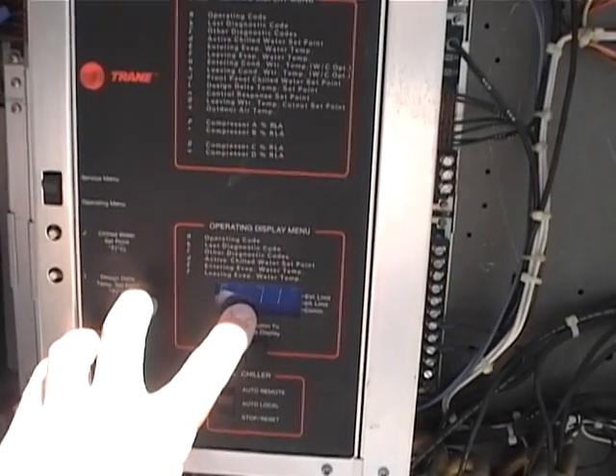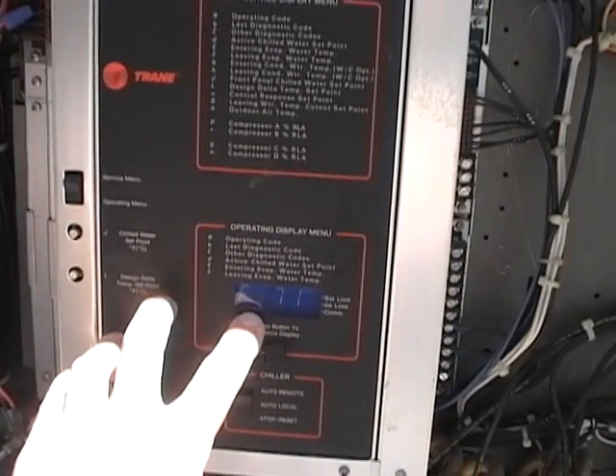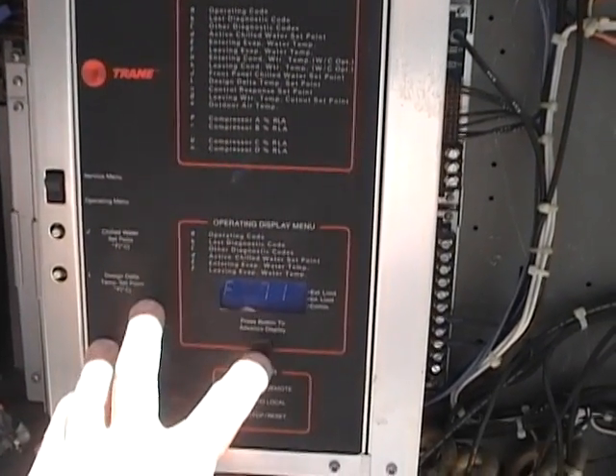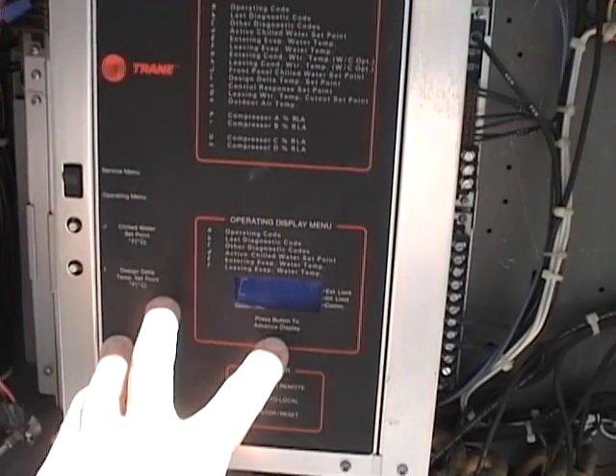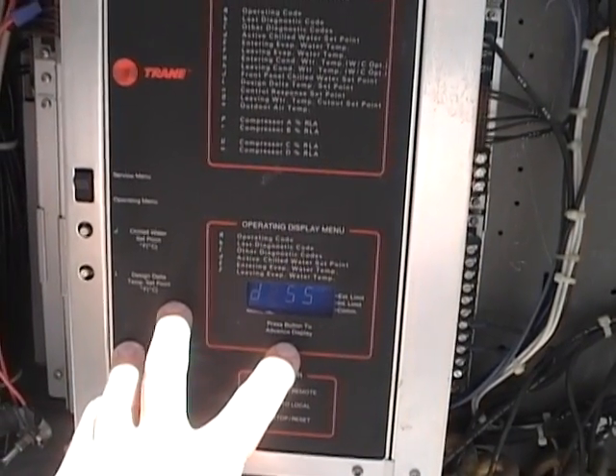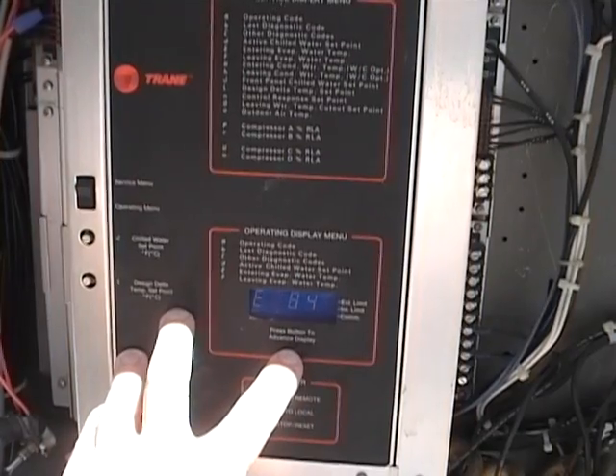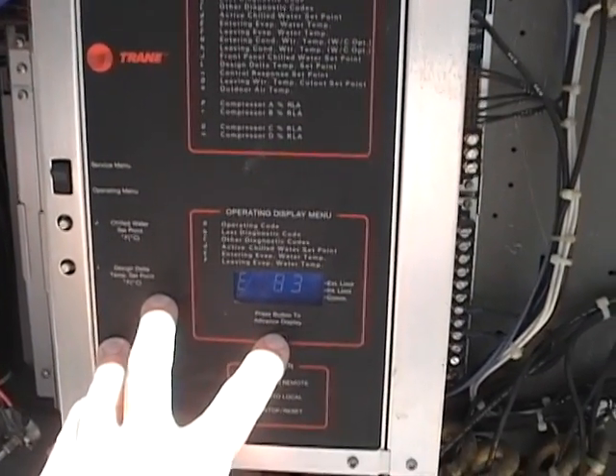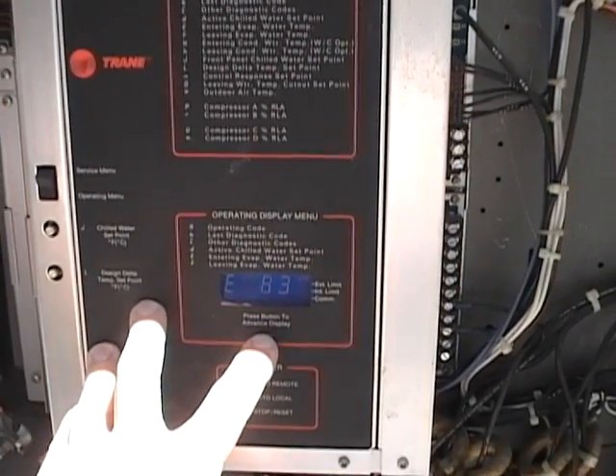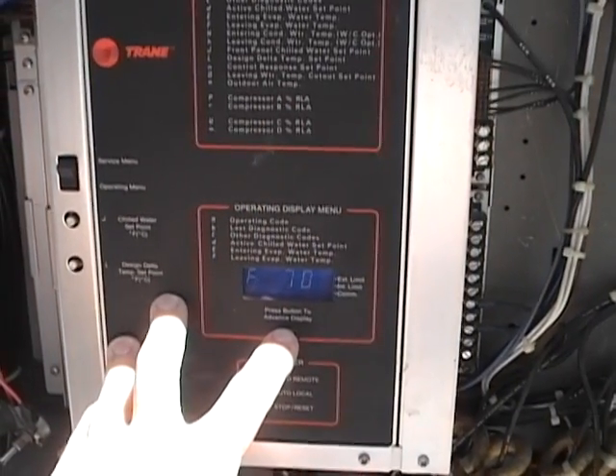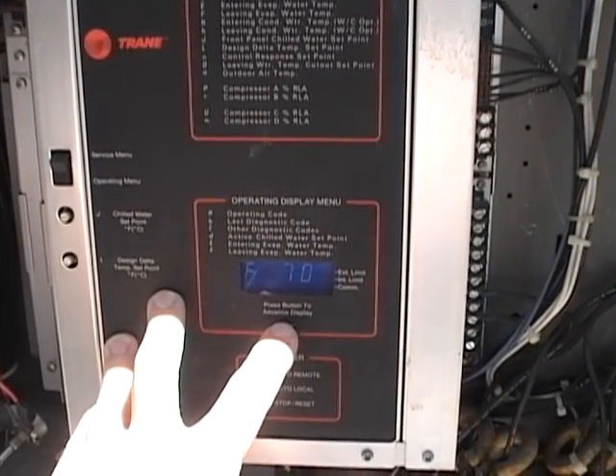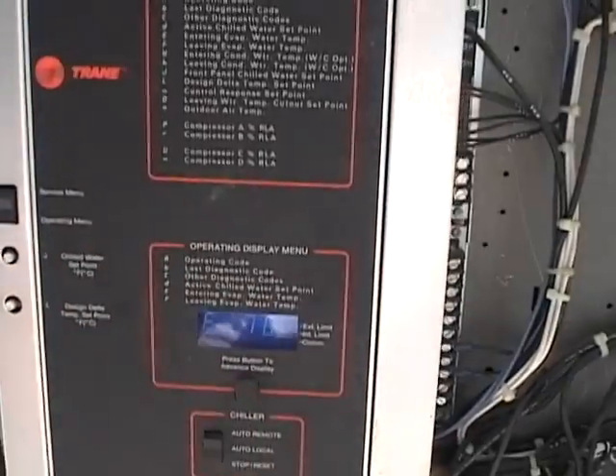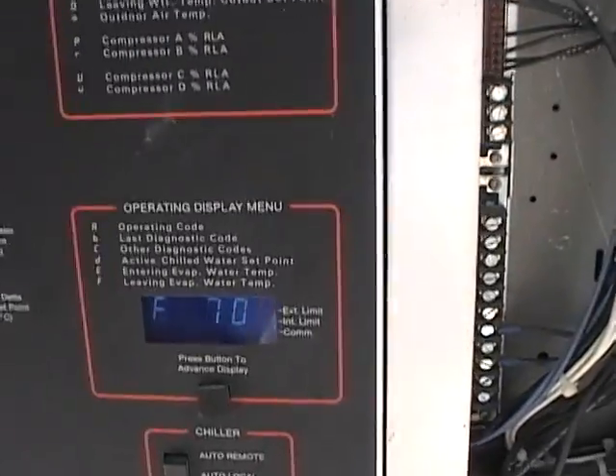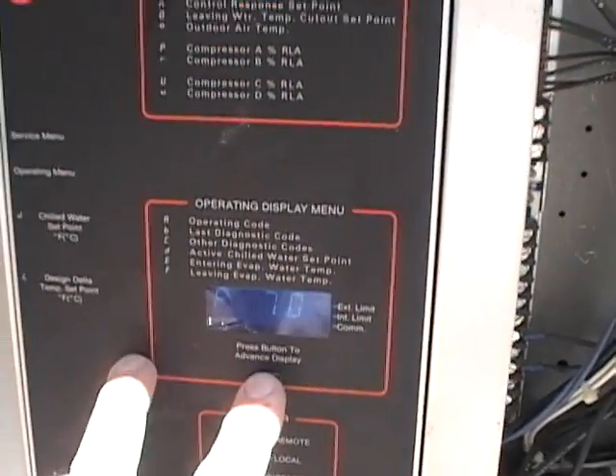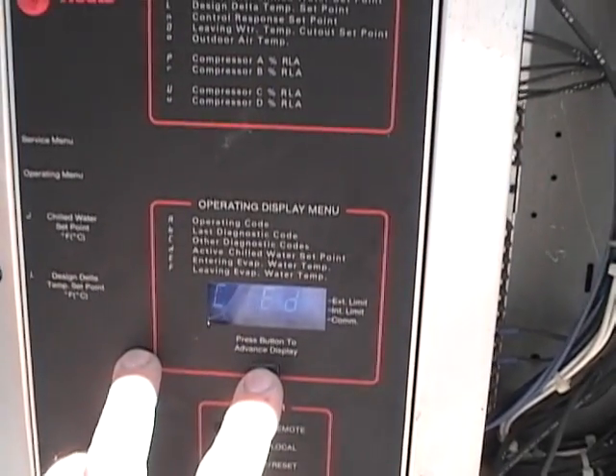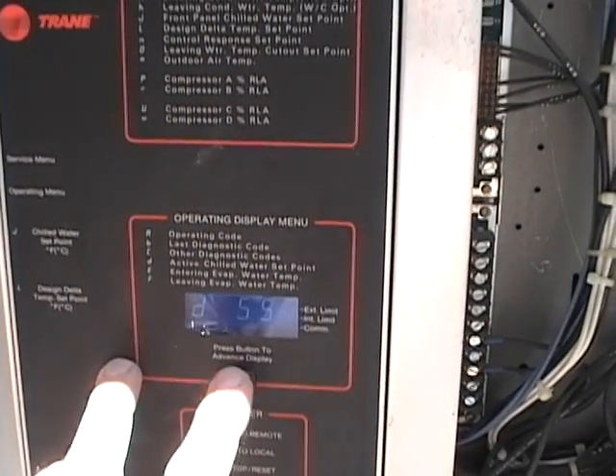F is the temperature leaving the chiller. So we're sending water out at 71 degrees. Our set point is 55. Our incoming water is 84. So now, as you can see, as we're putting cold water into the holding tank, it's dropping slowly. And our outgoing temperature is now 70. Okay? So we're just going to keep an eye on that outgoing temperature, and you'll see her slowly starting to drop. Okay? So once again, we scroll through, and D is our set point.